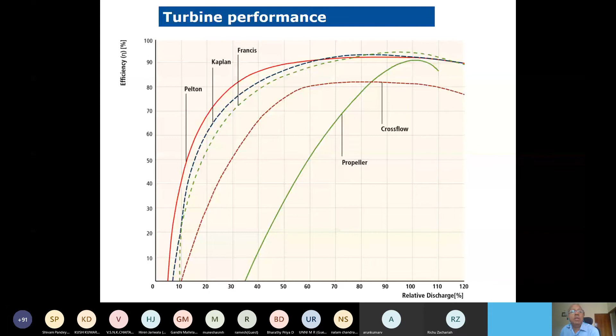During that zone there is a lot of noise, vibration, etc. So either you operate, or you see the efficiency drops very fast when it becomes lesser than 30-40%. These are the factors governing selection of turbines: head, discharge, specific speed, variation of head, maximum efficiency, part load efficiency, initial cost of civil works, number of units, running and maintenance costs, cavitation characteristics, and transportation limitations.